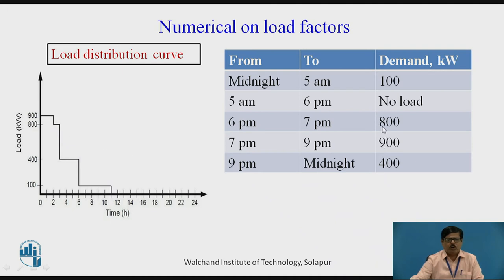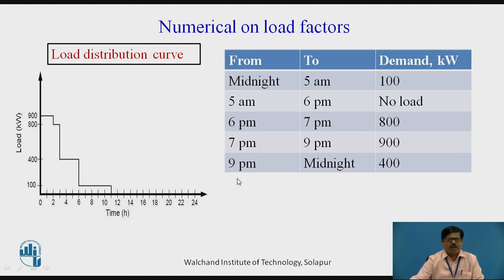Then the next lesser load was 800 KW from 6 PM to 7 PM, so for 1 hour I have drawn the horizontal line for 800 KW — after 900 KW, the load taken was 800 KW, that is in decreasing order. After that, the load of 400 KW from 9 PM to midnight is plotted for its time period. Then the load falls to 100 KW from midnight to 5 AM, so 100 KW is plotted for around 5 hours. This is how we arrange the loads in decreasing order to obtain the load duration curve. There is no load for the remaining period, so the further period is shown without any load.